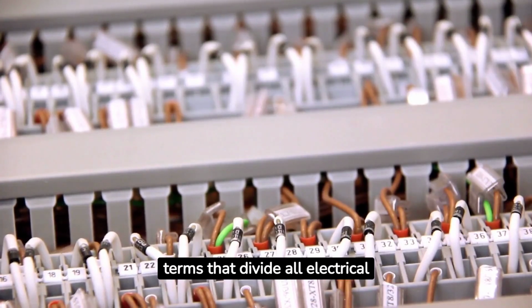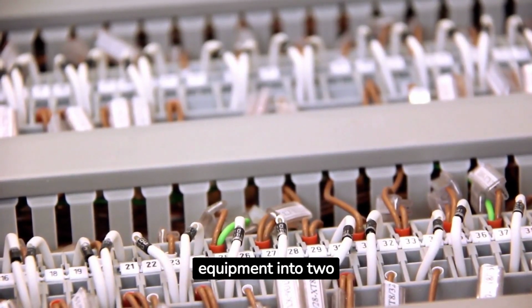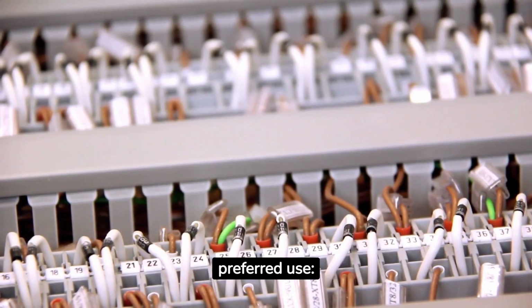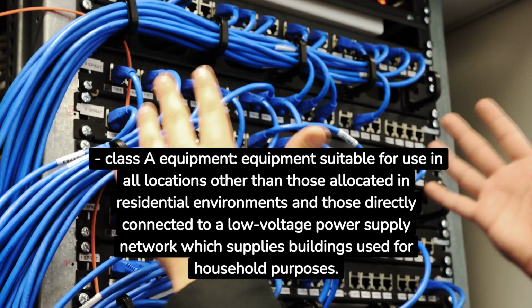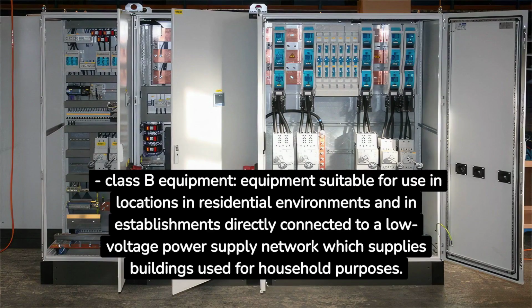61326-1-2020 defines two terms that divide all electrical equipment into two groups according to the area of its preferred use. Class A equipment. Equipment suitable for use in all locations other than those allocated in residential environments and those directly connected to a low-voltage power supply network which supplies buildings used for household purposes. Class B equipment. Equipment suitable for use in locations in residential environments and in establishments directly connected to a low-voltage power supply network which supplies buildings used for household purposes.